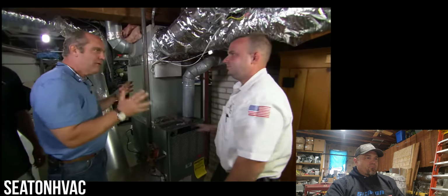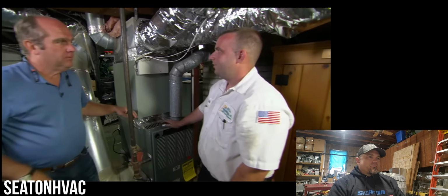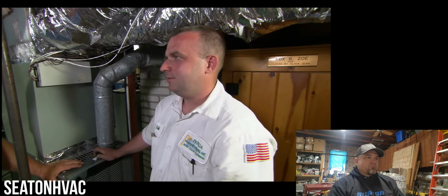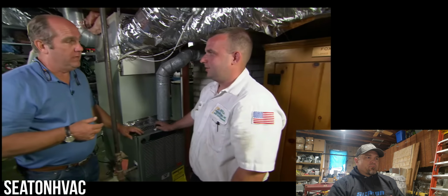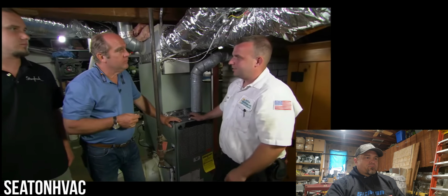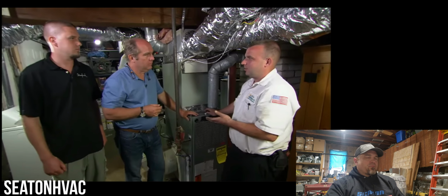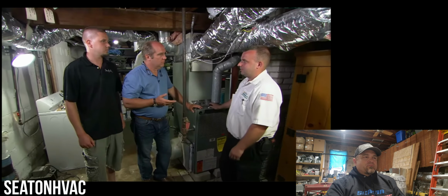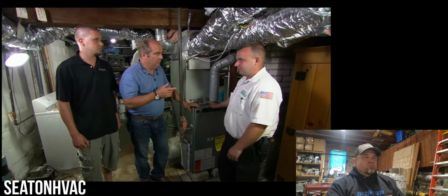So how do we get the right amount of refrigerant into this new system? Well, the new condensers that we install now, they all come pre-charged up to 25 feet of line set. And that's about what we have. So there's enough refrigerant in to cover our system perfectly without adding any more. That's exactly right. What I had to do, I had to evacuate the lines. Back when they used to give you 25 feet of refrigerant for your systems, now we're lucky if we get 15. And a lot of them are not charged fully. I've seen it many times. After they're evacuated, all I have to do is just open up the lines on the condenser, and it's pre-charged. Right, so we're good to go? That's it. All right, ready to go.